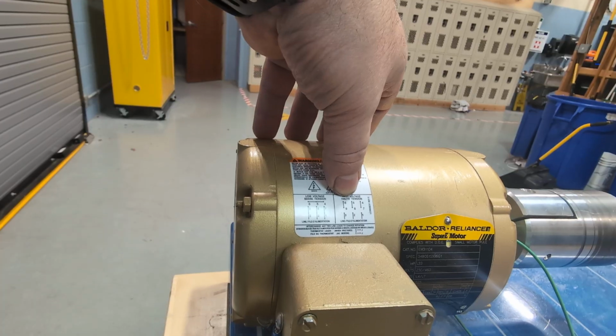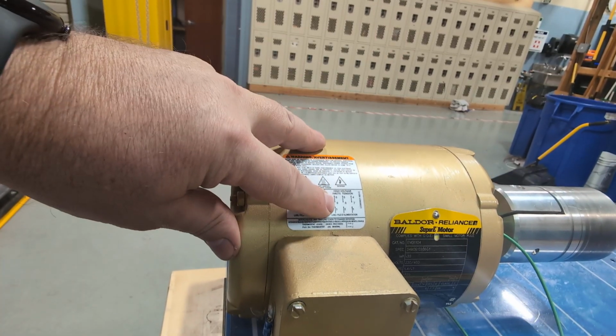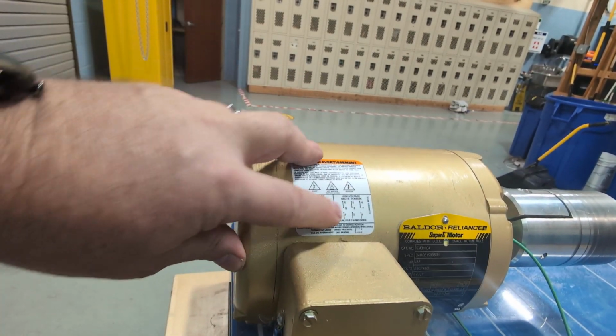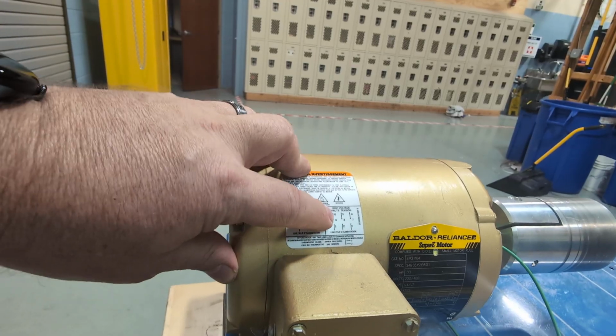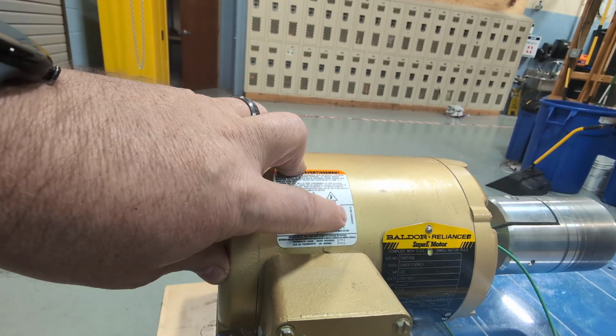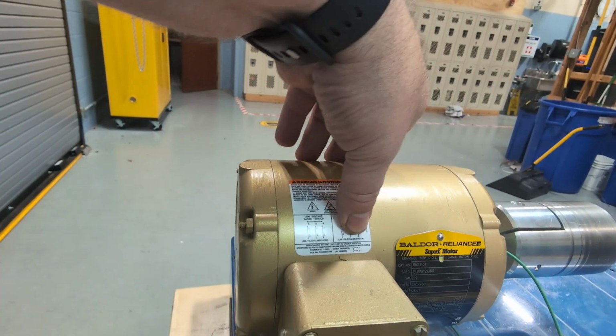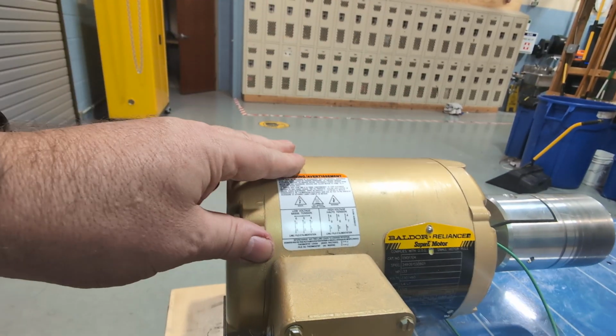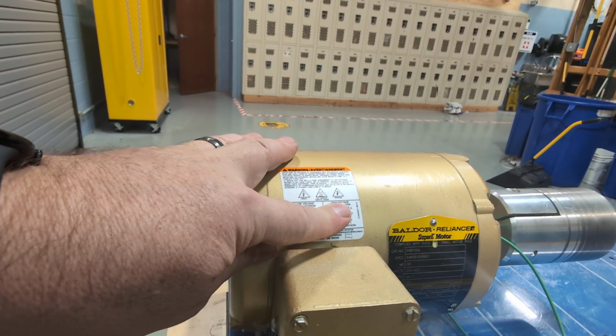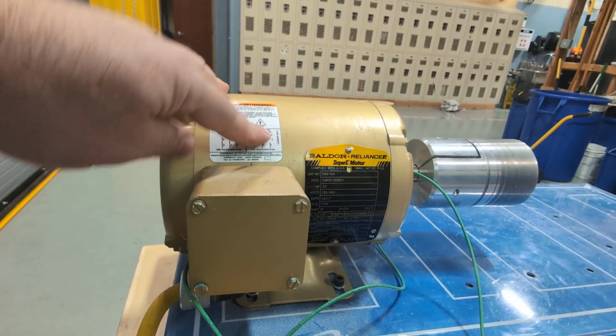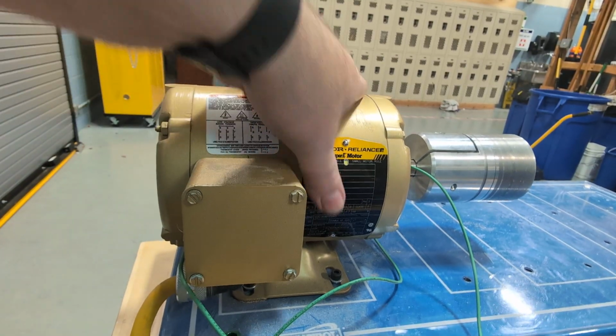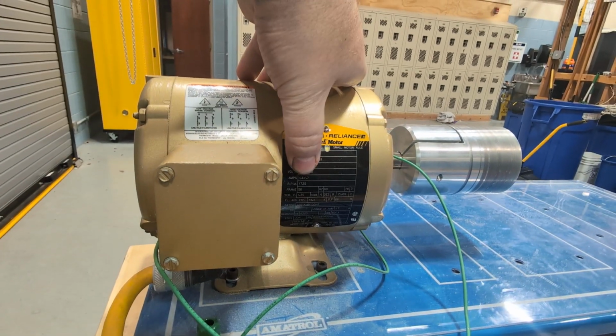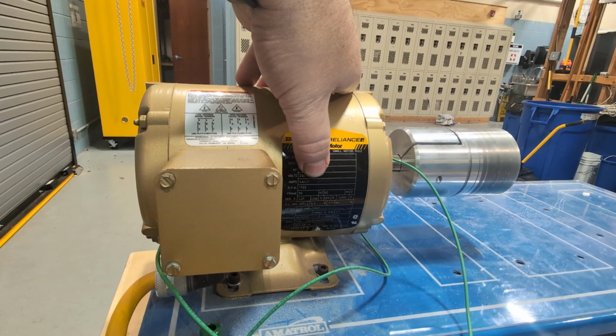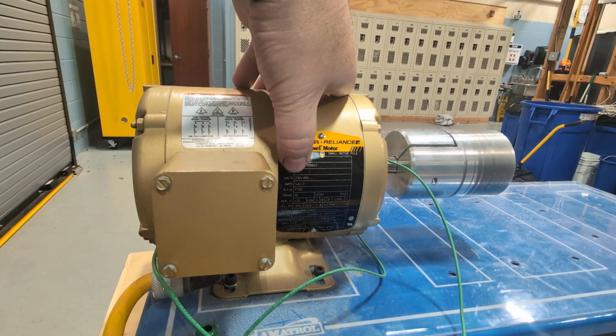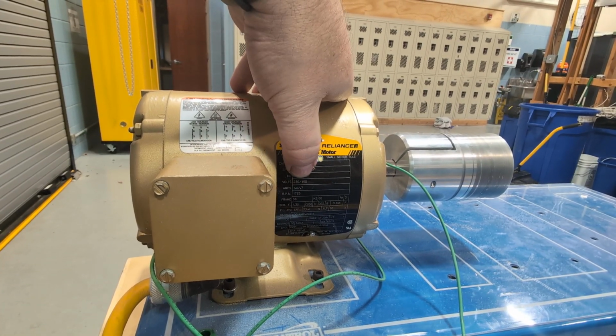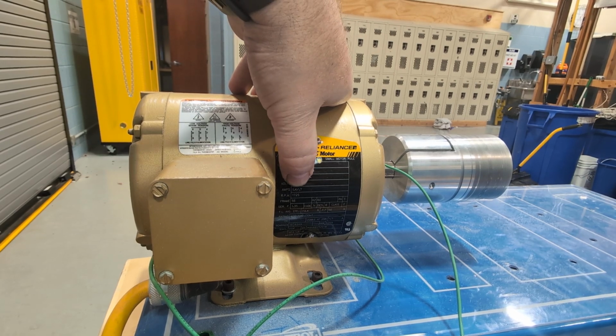When I do high voltage, this is what I'm doing. 6 and 9, 5 and 8, 4 and 7, 3, 2, 1. These get wire nutted together, wire nutted together, wire nutted together, and my wires get connected to 1, 2, 3. That's if I have high voltage. This motor is a 0.3 horsepower motor. The amperage is 1.4 to 0.7. The higher amperage, that's why I'm showing, 230 is 1.4. Higher voltage, 460, is 0.7.